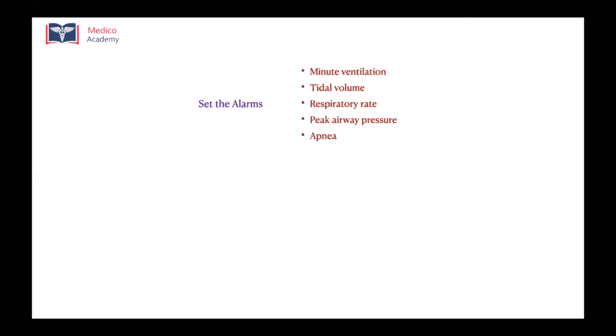And also there will be an alarm for apnea. Suppose you have put the patient on a spontaneous mode like pressure support ventilation, there will be an apnea alarm. You can set it between 10 to 60 seconds. Usually for adults, we keep an apnea interval of 20 to 30 seconds. So if that happens, the ventilator will have some backup settings.